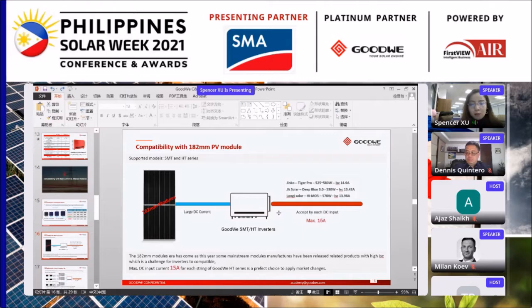We can see that the mainstream 182 millimeter manufacturers have a short circuit current of about 13 to 14 ampere. And we found that even the one from Jinko that has the largest short circuit current of 14.9 ampere is below the 15 ampere of our inverter. It can support a maximum 15 ampere input current per string, and it can already be a mainstream combination for the 182 module and HT inverters. So we can say that we are fully adapted to 182 millimeter PV modules.